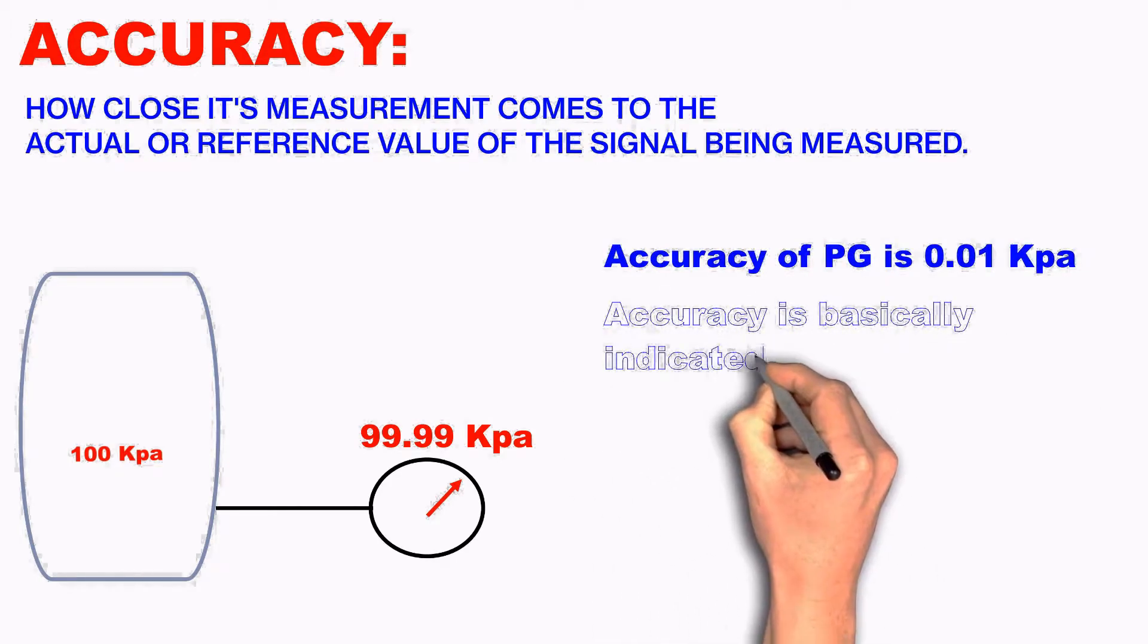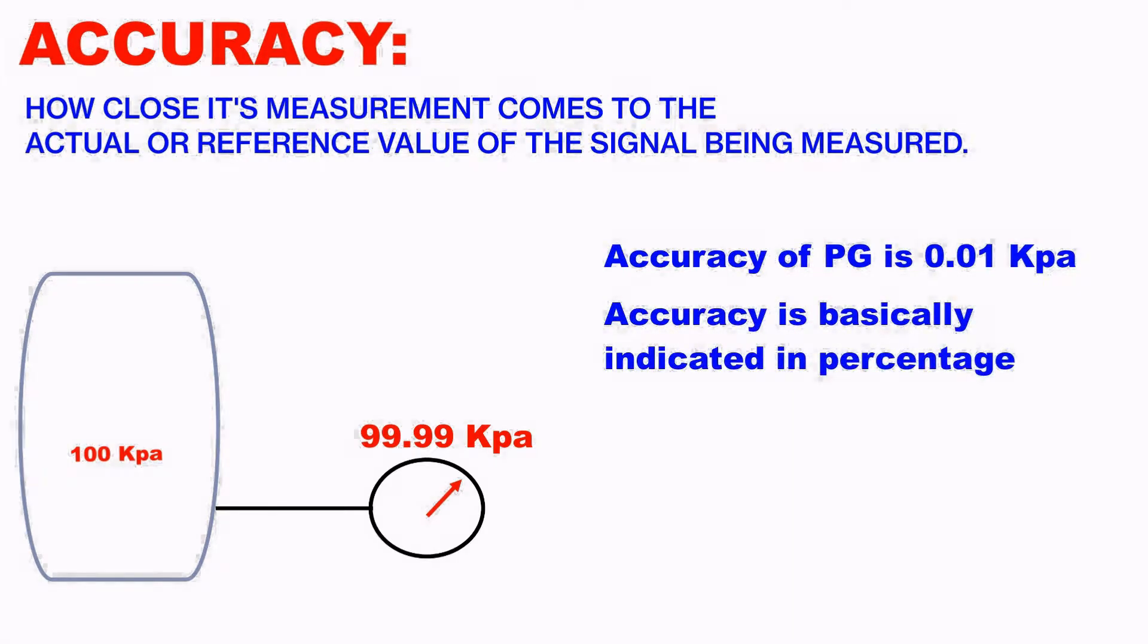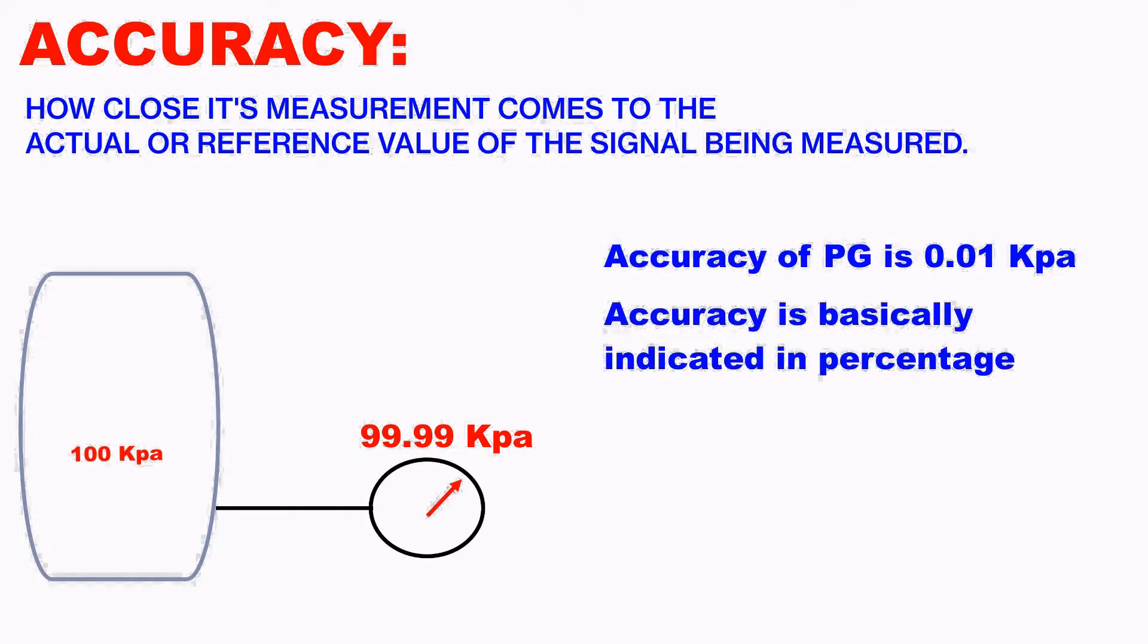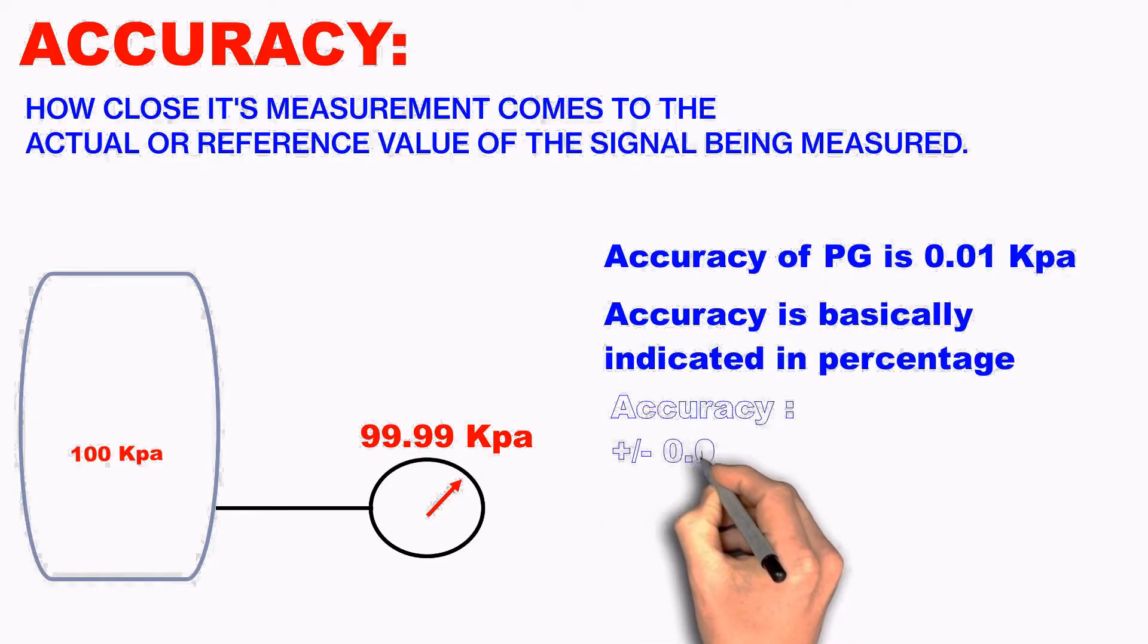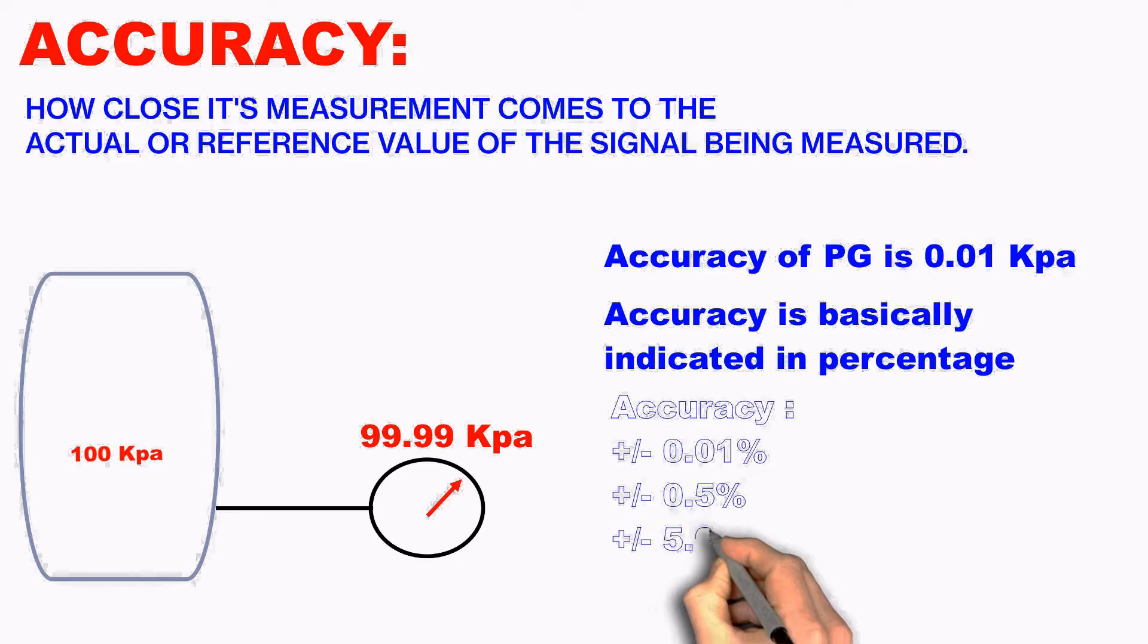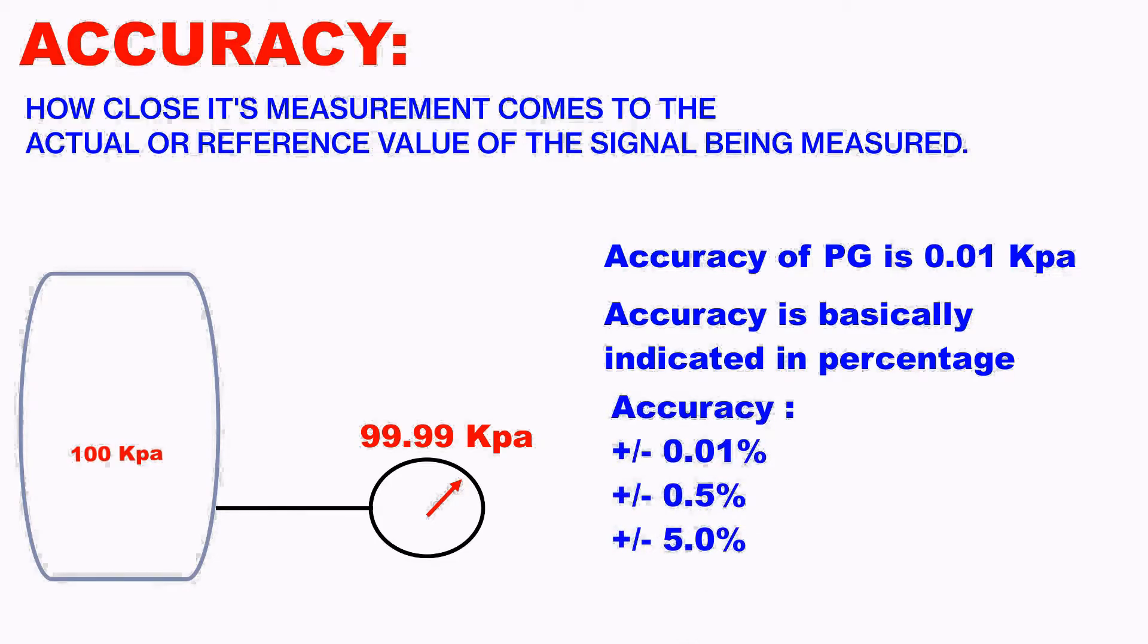So the accuracy level for 0 to 100 range is 0.01. Basically, accuracy is being indicated in percentage. Some of the equipments will come with a standard accuracy percentage like plus or minus 0.01%, plus or minus 1%, plus or minus even 5% is available. So this is the accuracy, and next let's see resolution.